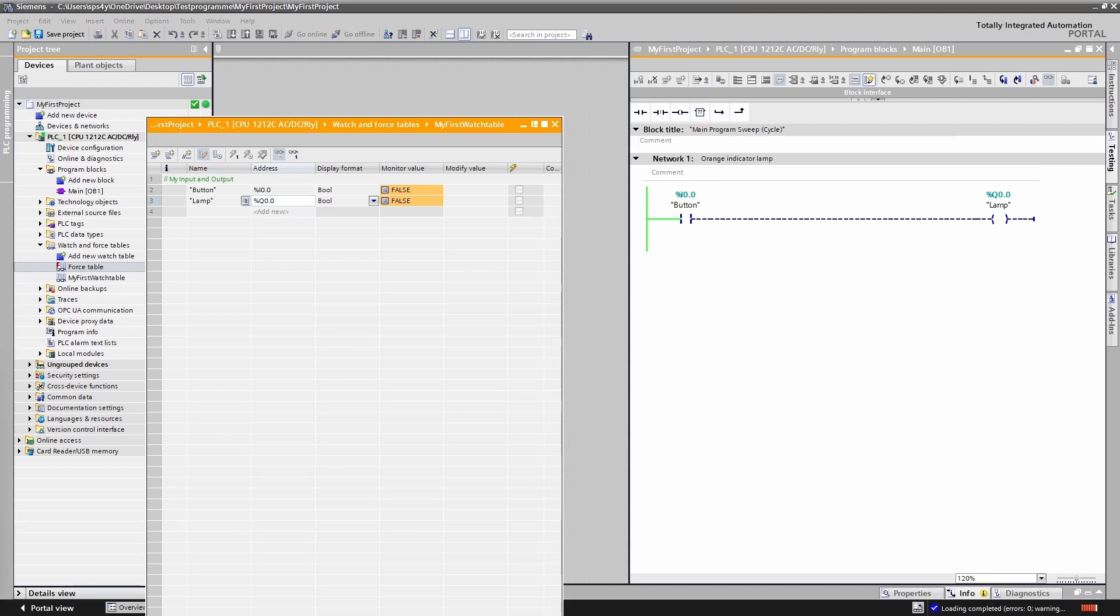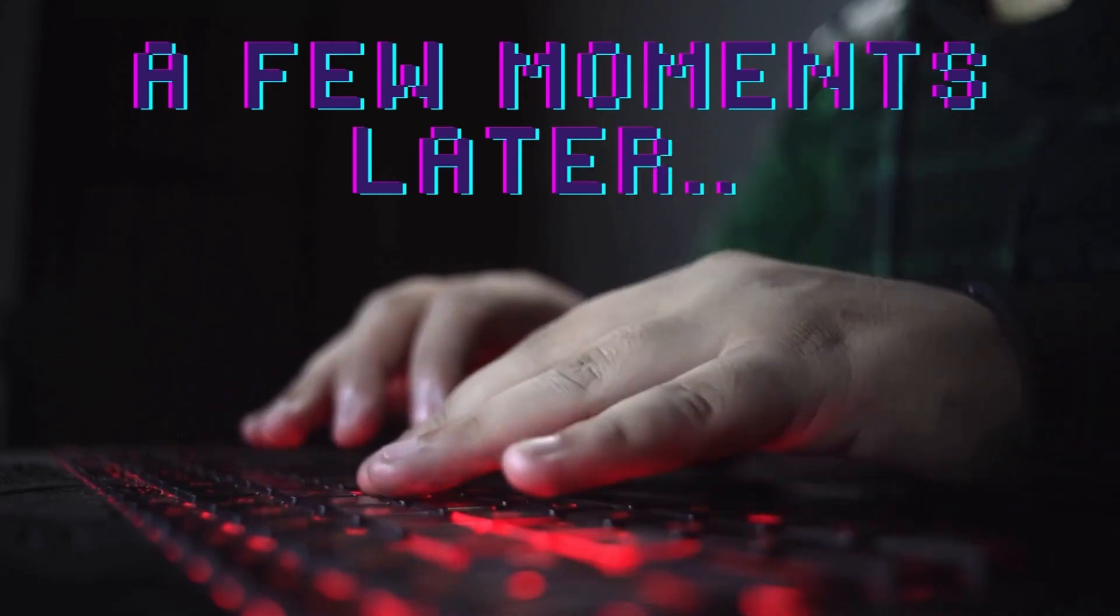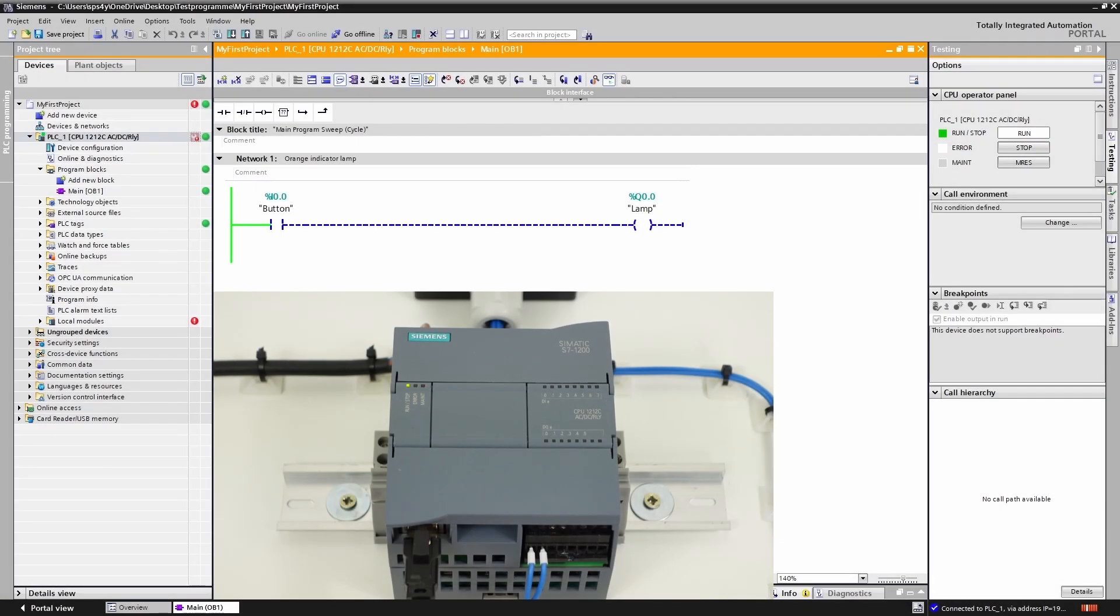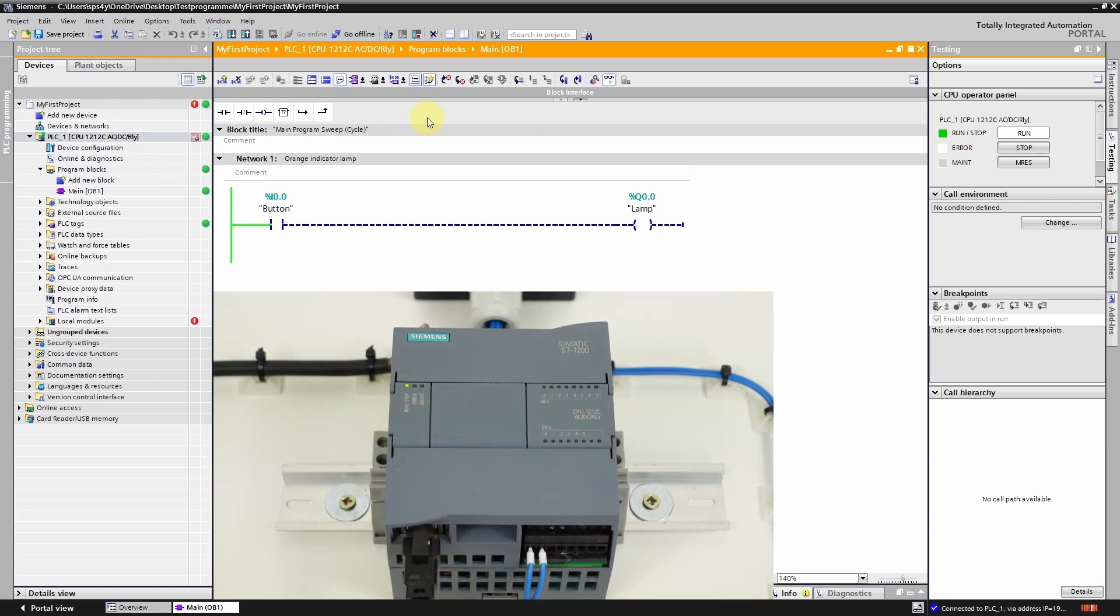At the end of this video I want to show you another important feature in the TIA Portal. Give me a few seconds to set it up. Welcome back. As you can clearly see our PLC has an error. I want to show you how to identify and resolve such errors. To do this navigate to the diagnostic buffer of your controller. You can access it by double clicking on this symbol.